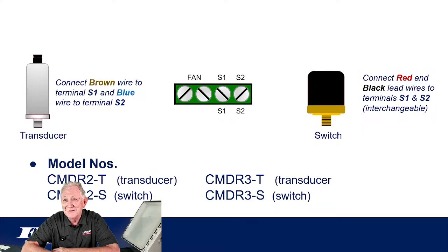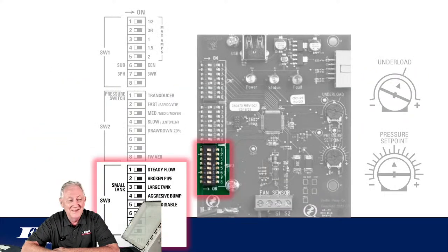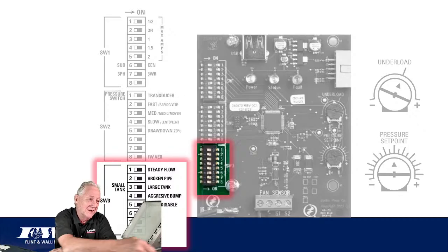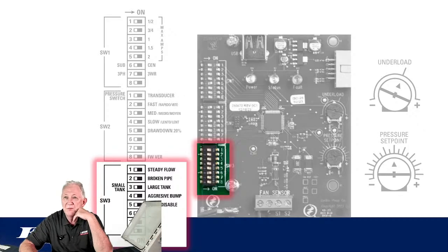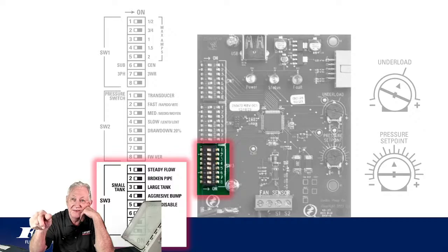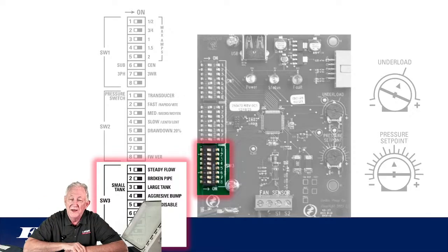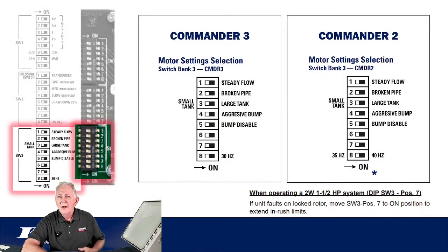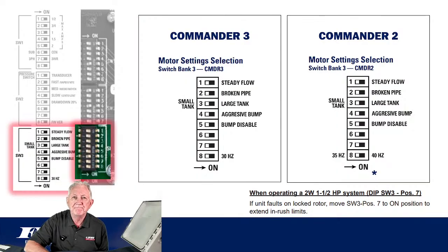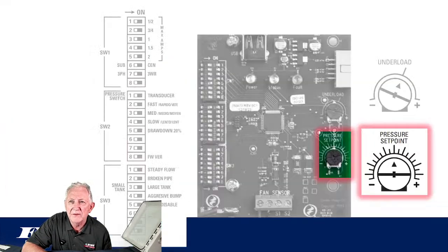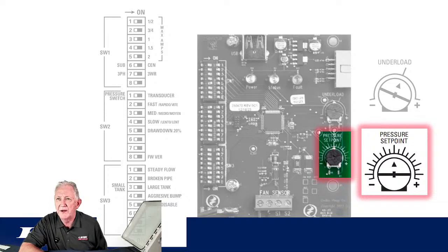Whereas with that dial down here in the bottom right-hand side, where the pressure set point is, that's why a contractor tends to like this. They said, man, this is so much easier to set the pressure because I don't have to look at a gauge. I just open the enclosure and, with that dial, choose my pressure set point. Now, I do want to talk about this pressure set point real quick.